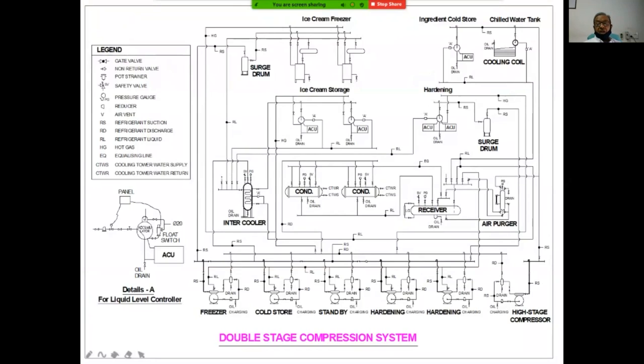These are the compressors. These are all compressors. These are condensers. You can see from the condenser the liquid refrigerant is going to the receiver. There is the air purger to remove the non-condensable gases, whatever enter inside the system due to leakage. There is an intercooler for subcooling of liquid. Means whatever we learned, all the processes are done here, and the subcooled liquid goes to the evaporators. These are the evaporators. These are also evaporators. You can consider here all are evaporators.